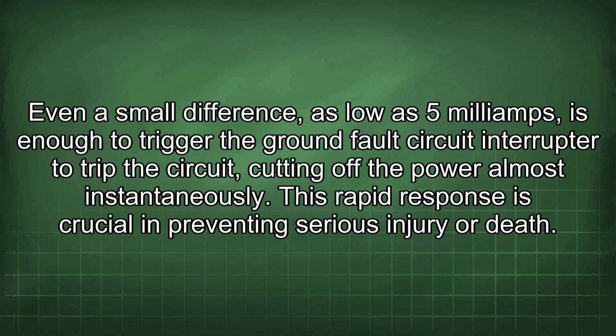Even a small difference, as low as 5 mA, is enough to trigger the ground fault circuit interrupter to trip the circuit, cutting off the power almost instantaneously. This rapid response is crucial in preventing serious injury or death.